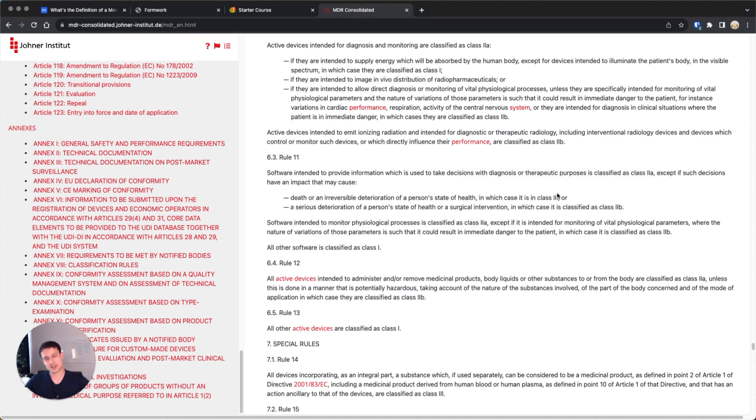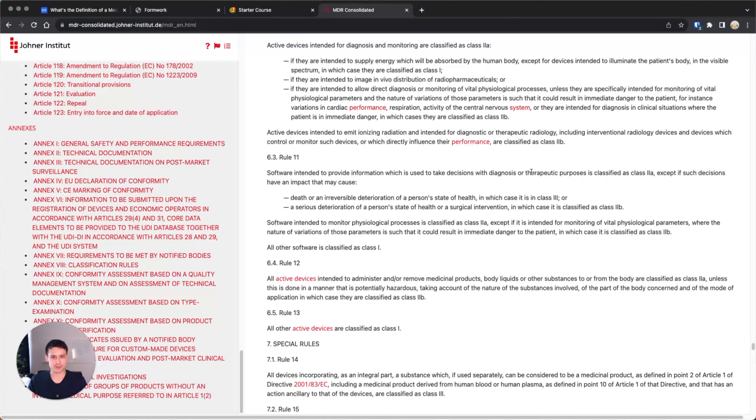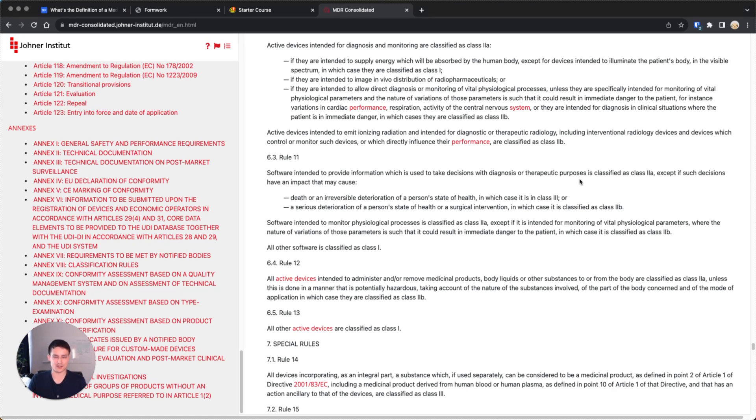I'm going to skip through everything here and just read the last sentence, which is, otherwise the software is class 1. If you provide this information, you're class 2a or higher. If we go back to our examples, like Vara doing breast cancer screening, sounds like information to take decision with diagnostic purposes. So, probably class 2a or higher.